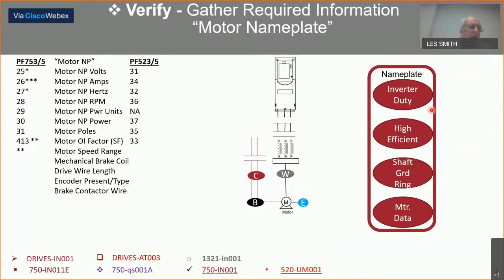In each drive, you're going to have motor nameplate data. And as you see, you've got the volts, the amps, the hertz, the RPM, the power units, be it watts or horsepower, and then the power level that you're going to put in there. The number of poles, please don't put down 3 poles. I see that so many times. And motor overload factor. Take a look at motor overload factor on the 753. That's on parameter 413. That's 400 parameters away. You may miss that sometimes.